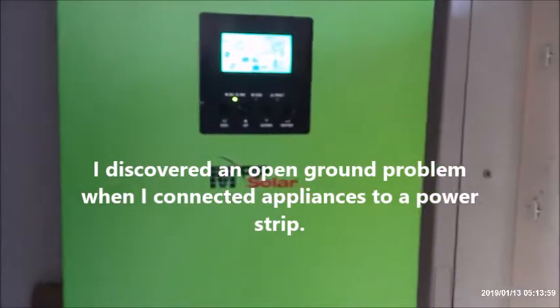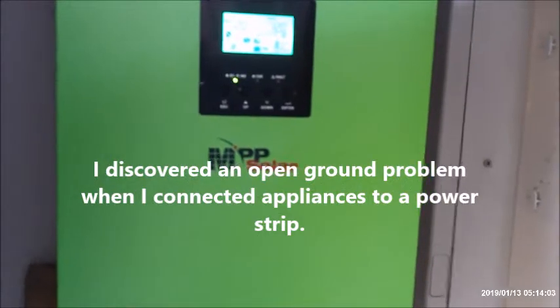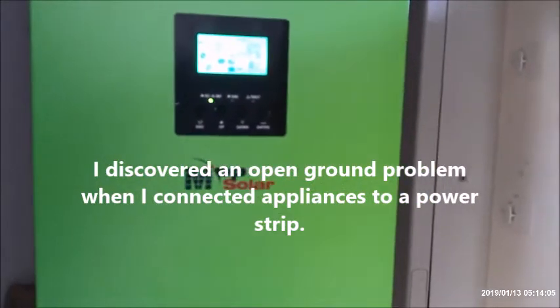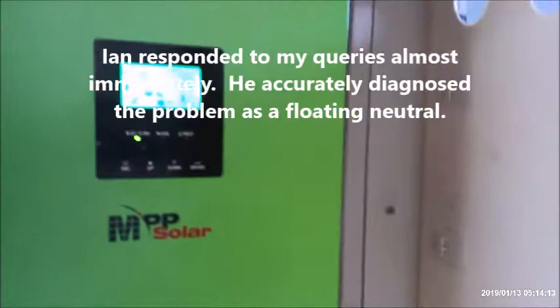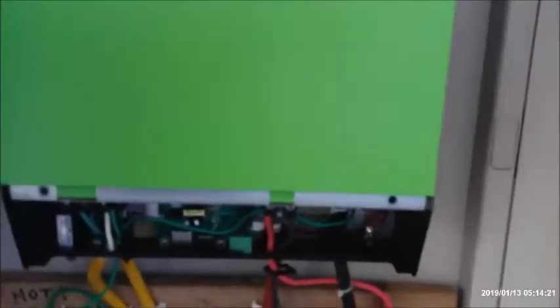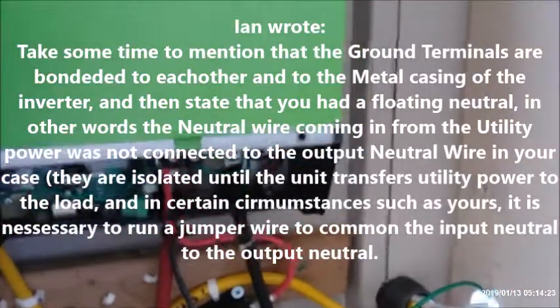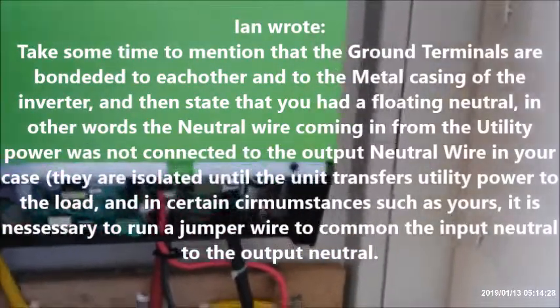I bought this 2400 watt 24 volt hybrid inverter from USA MPP Solar, I believe owned by a gentleman named Ian, and it's been running great. But I noticed when I connected it to a power strip inside the house, I had an open ground.